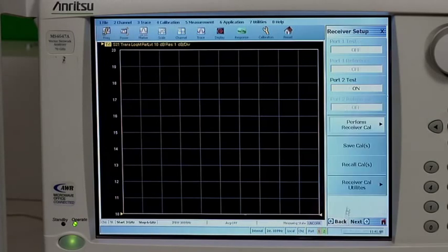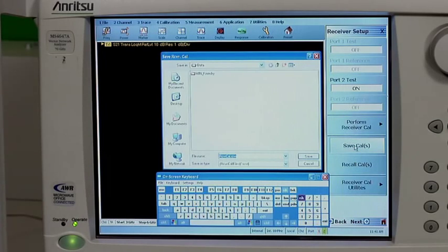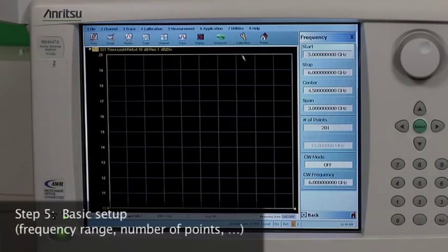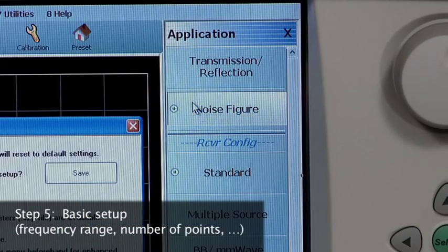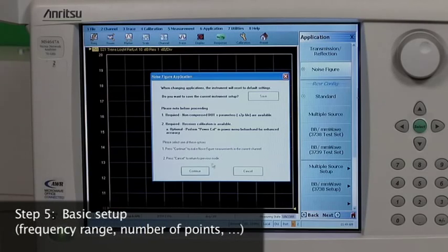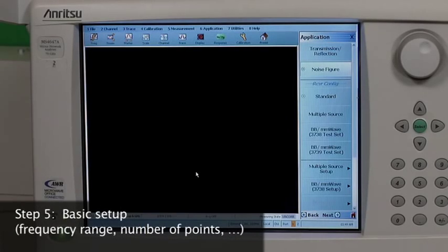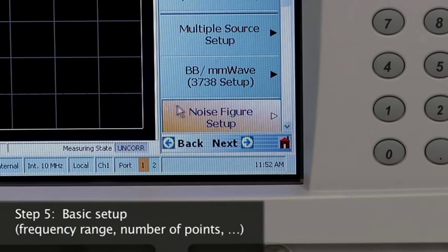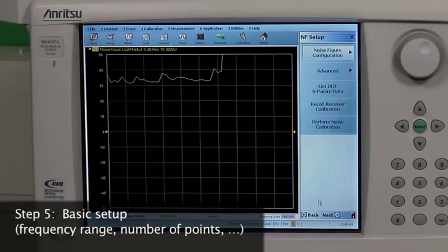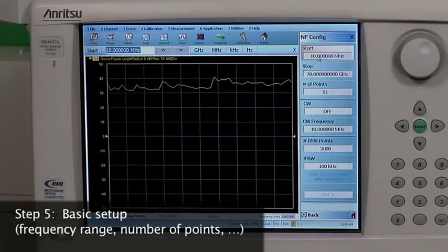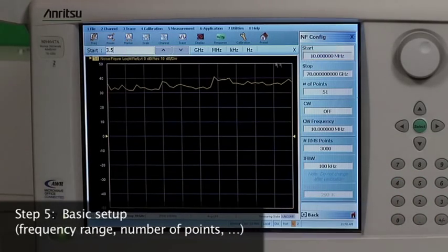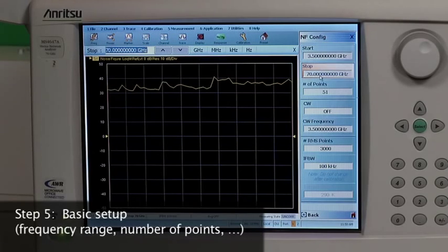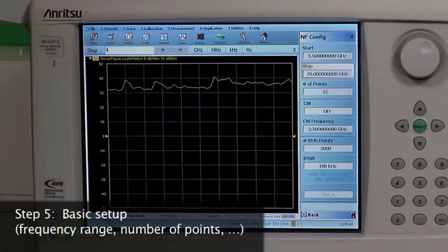When complete, we saved the receiver calibration. We are now ready for step five, noise figure measurement configuration. For this demonstration, we are going to measure the noise figure of our amplifier from 3.5 to 4 GHz, with 201 frequency steps and 3,000 RMS points per noise computation. Trade-offs can be made between the measurement speed and data jitter by adjusting the number of RMS points.